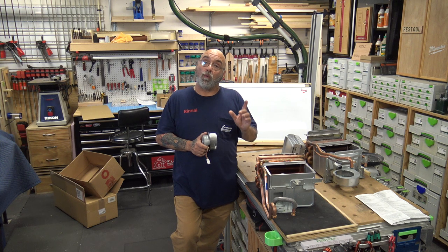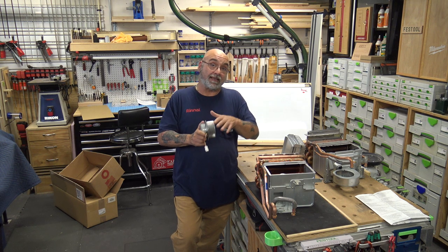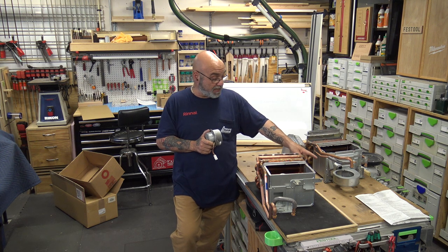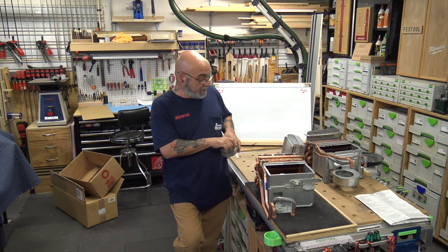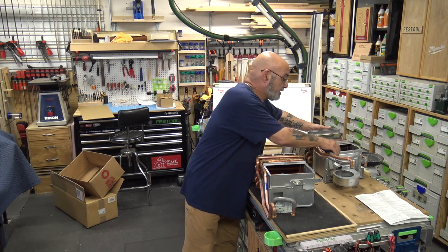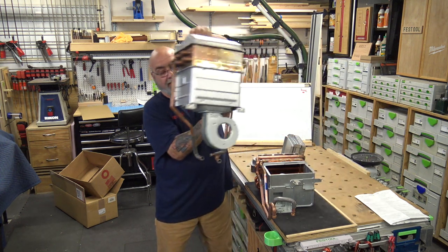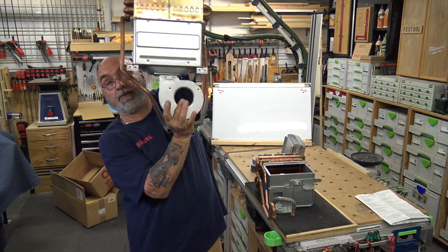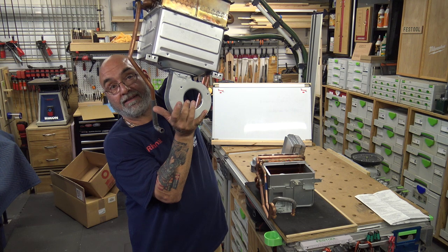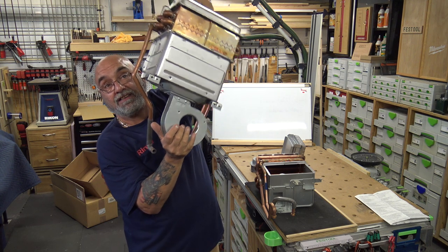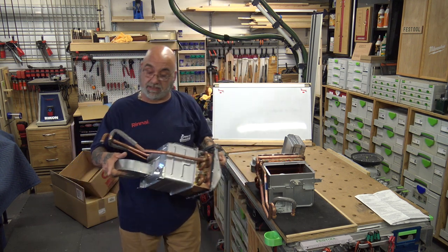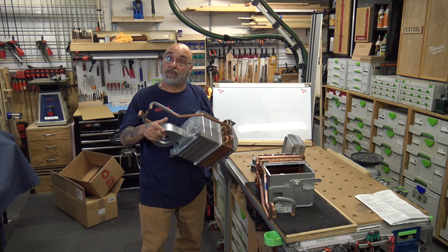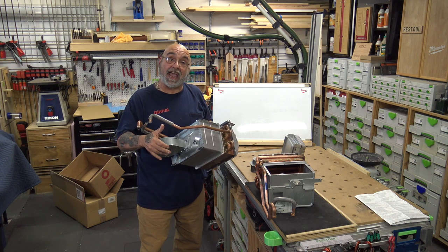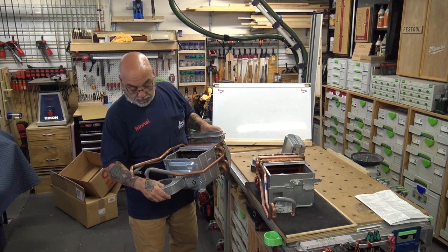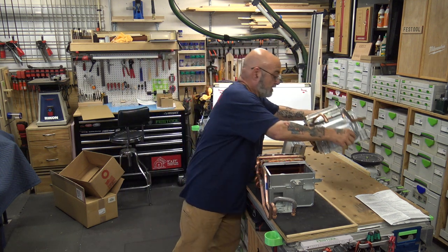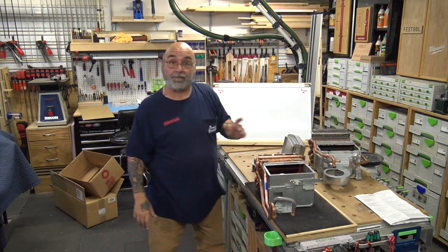But when you have the fan out, get in there with your flashlight and check the fan box. You see here on an exterior unit, that's where the air is being brought in, right there. It goes in through the chassis. If you look on an exterior unit, there's louvers on the bottom of the front cover, and that's where the air comes in through the back. So you want to check this fan box for any debris in there.